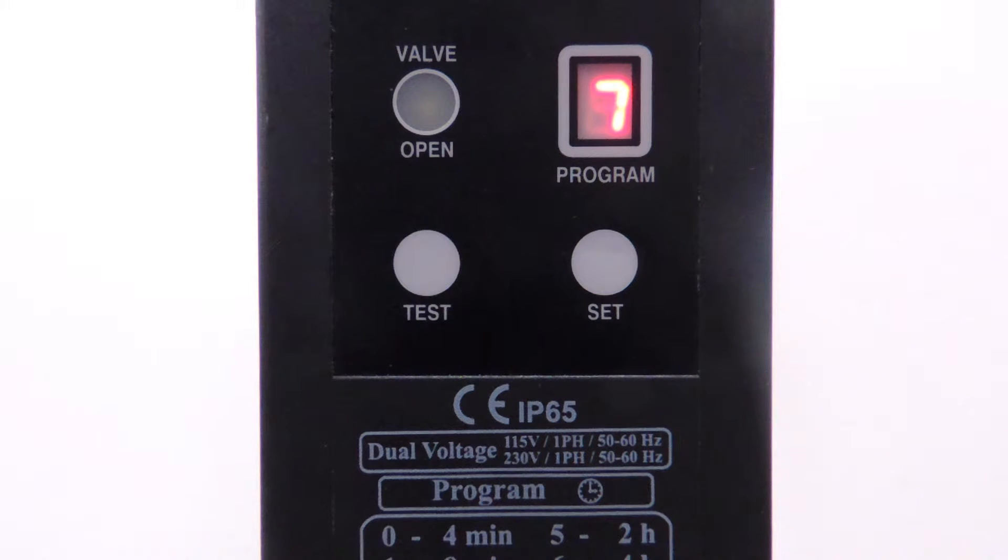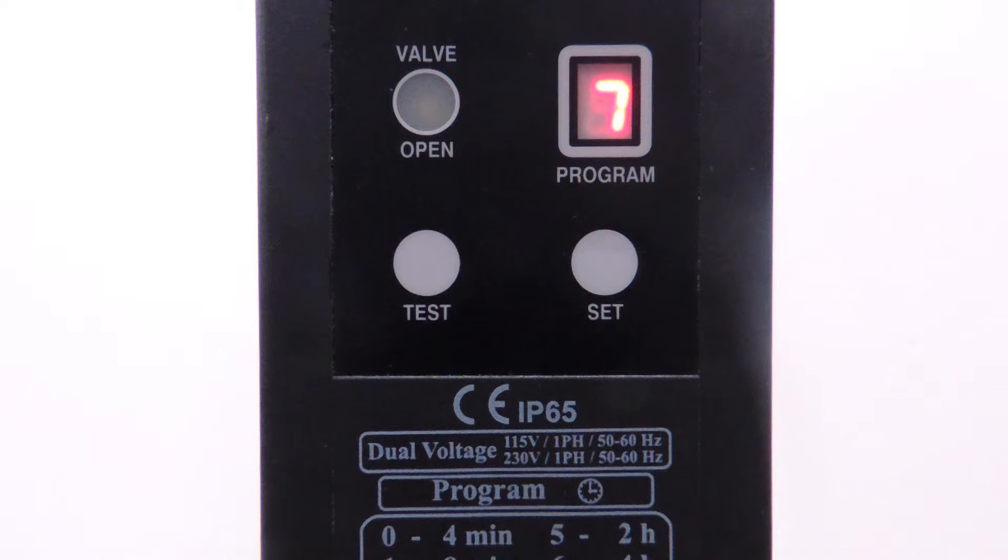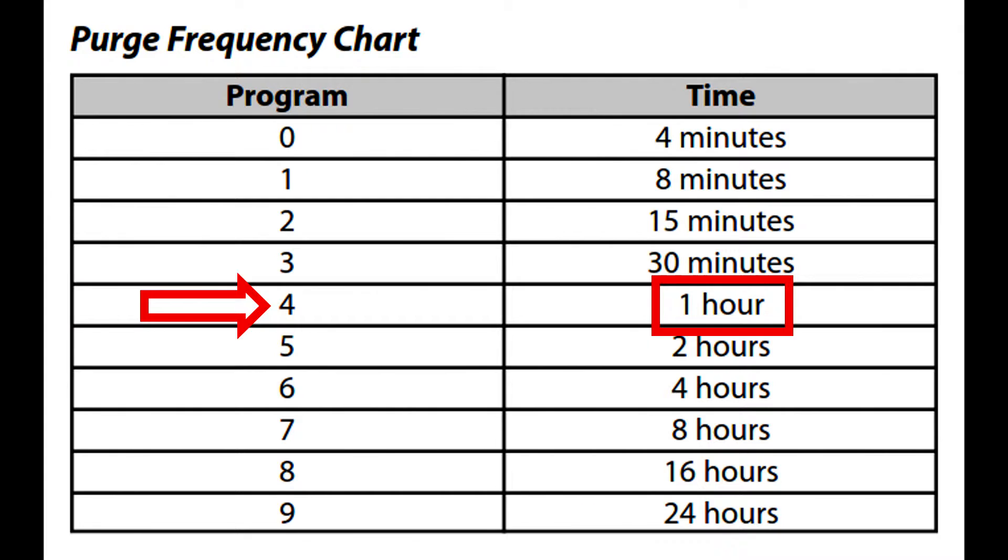Let's try an example. Say we want to set the valve so the unit purges for 30 seconds every hour. First, we're going to look at the purge duration settings chart. We want to use setting F for a 30-second purge duration. Next, we look at the purge frequency settings chart. Setting 4 will give us the desired purge frequency of 1 hour.